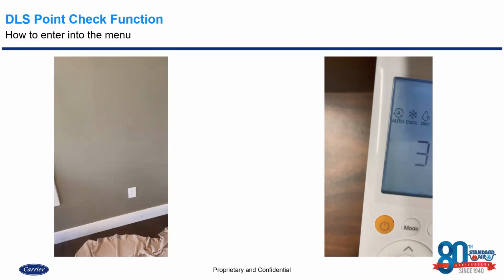Okay, so now we know that we're going to see those R values come up. You may have noticed that there was a number out of there that said 75 or 34. That is a temperature in degrees Celsius. You need to make sure that you convert over into degrees Fahrenheit. Now, I have done a few tests on these new 40 M8H units. They should display in degrees Fahrenheit now. However, if you do get a number that seems awfully odd, chances are you are probably getting a degree Celsius, especially if it's reading 30-something degrees and it's in the heating mode for coil temperature. Okay, so again, they should read out as a default in Fahrenheit now with the new product update. However, that doesn't always necessarily mean everything's perfect, and sometimes we have issues with the software. So it's important to note, if you're getting a temperature in degrees Celsius and you suspect it depending on the mode, make sure that you convert over to Fahrenheit.